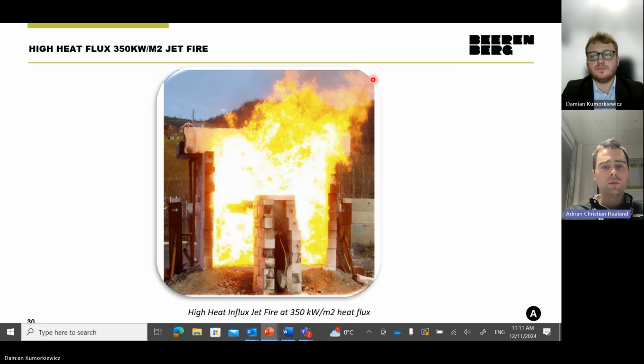So it's really on the edge of what removable PFP systems can do. In some tests, you go beyond the point where steel starts to melt. So not every fastening component can do it, and it's really pushing the limits of both what is physically possible to generate in terms of heat in a fire, and also what is possible for a system to withstand. And it is vastly different from a standard jet fire. In a standard jet fire, you can pass 2 hours for a system. You put it into a high heat flux, you can fail after 10 minutes because everything falls apart due to the high temperature. So it is quite different, and you can't interchange the two methods.